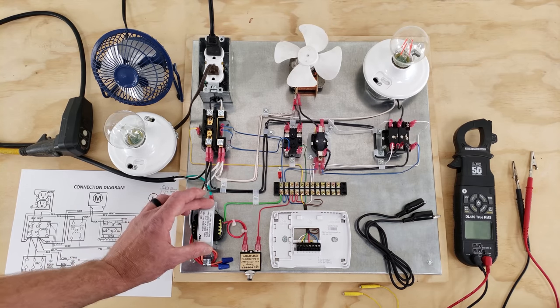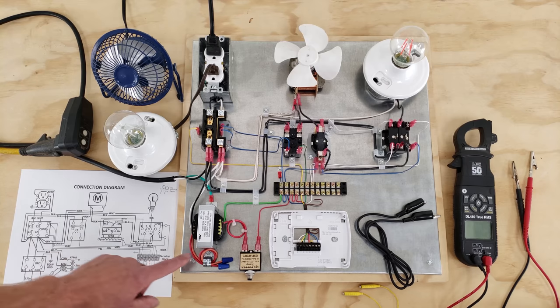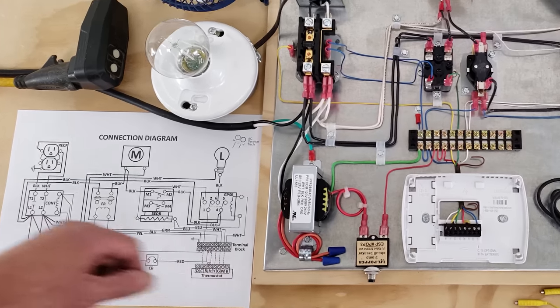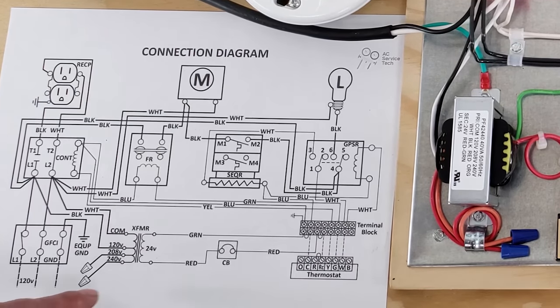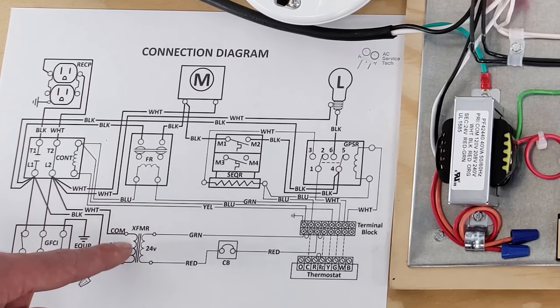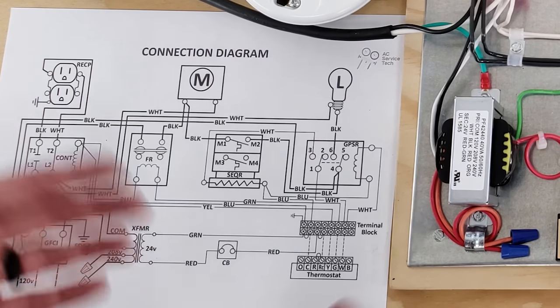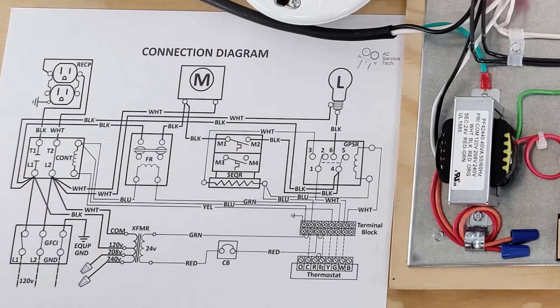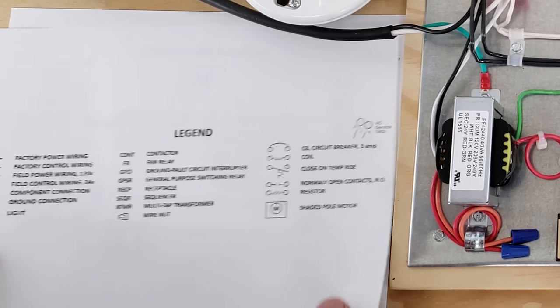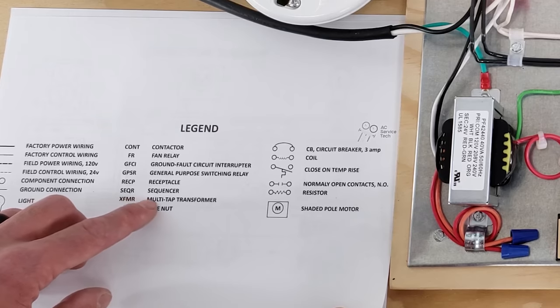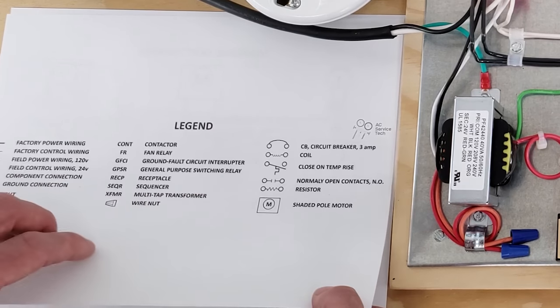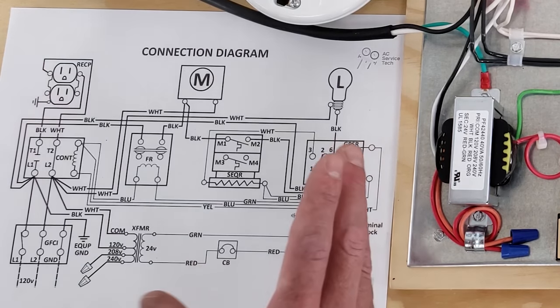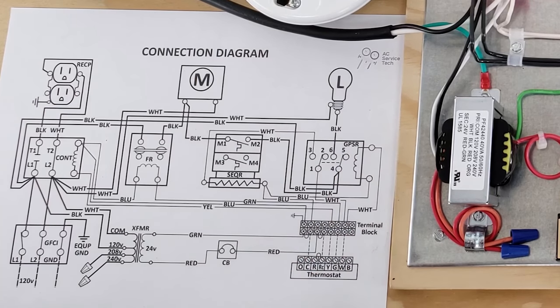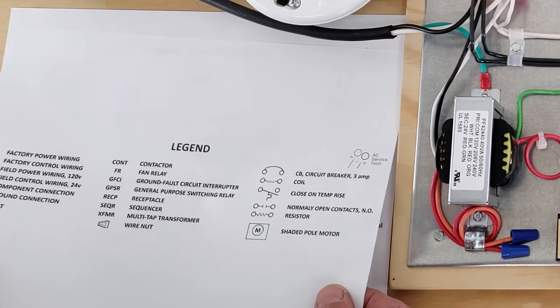So here we have a multi-tap transformer. We have two wires that we're not even using, and we want to have those in wire nuts. You can see that right here on the connection diagram, XFMR. Well, what is that? We just take a look at our legend and we can see that XFMR is a multi-tap transformer. So anytime that you don't understand something on a wiring diagram, you want to look over at the legend to determine what that is.